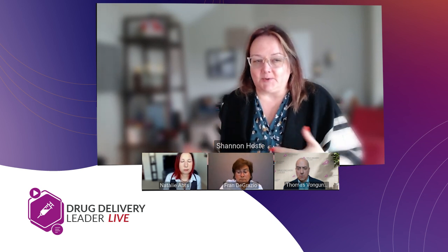The challenge personally that I have with the UFMEA is there's a standard out there for FMEAs. It's IEC 60812:2018 that outlines that as very much an engineering tool looking at failures. And so as you're following that, there are some assumptions that go into a typical FMEA, like single point failures and the like, and sometimes that can run into tension.